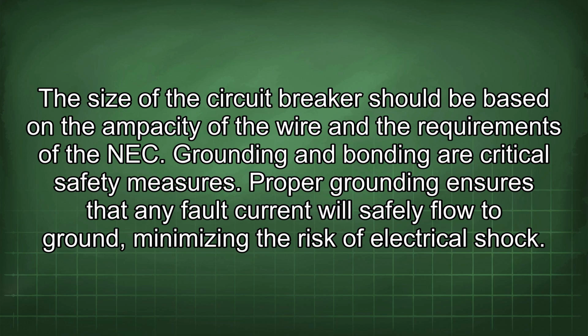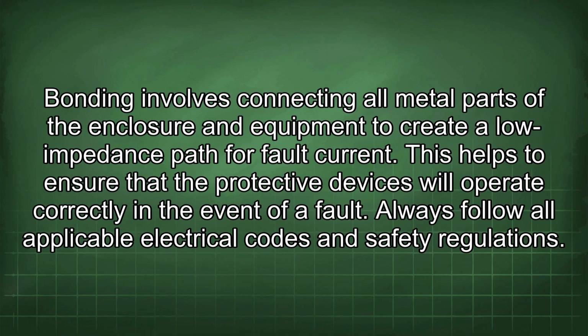Grounding and bonding are critical safety measures. Proper grounding ensures that any fault current will safely flow to ground, minimizing the risk of electrical shock. Bonding involves connecting all metal parts of the enclosure and equipment to create a low impedance path for fault current. This helps to ensure that the protective devices will operate correctly in the event of a fault.